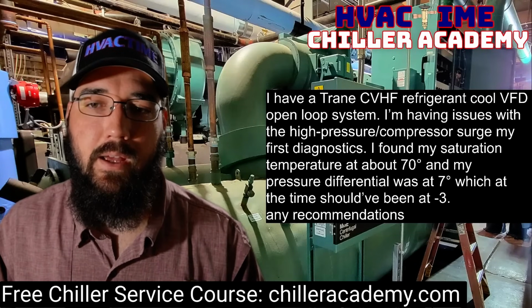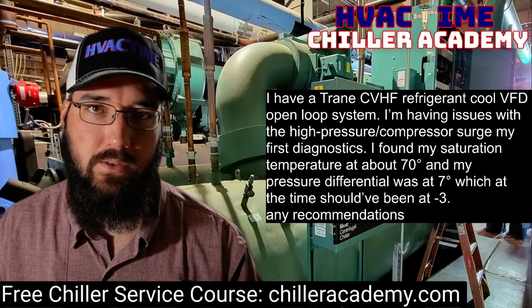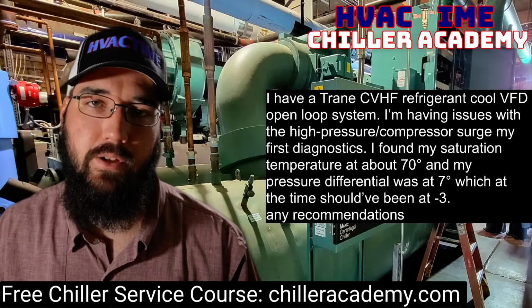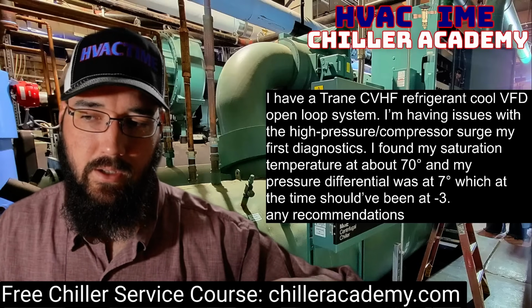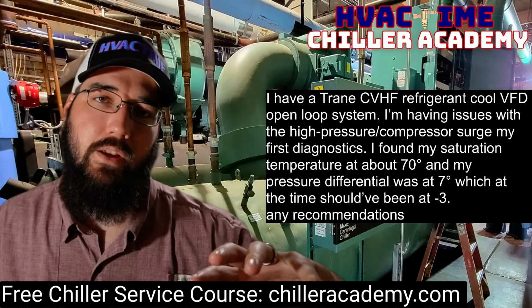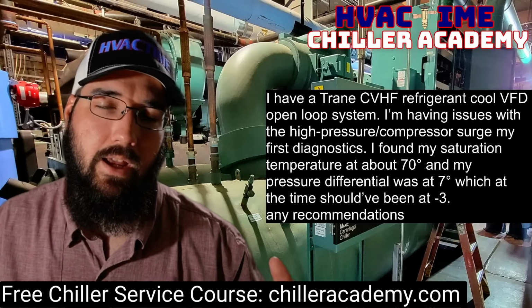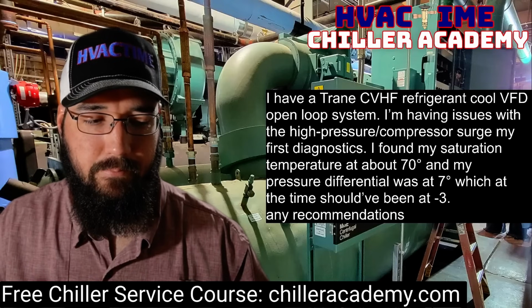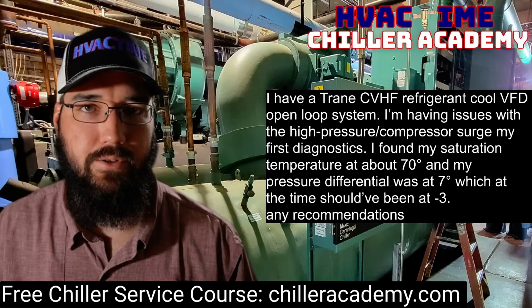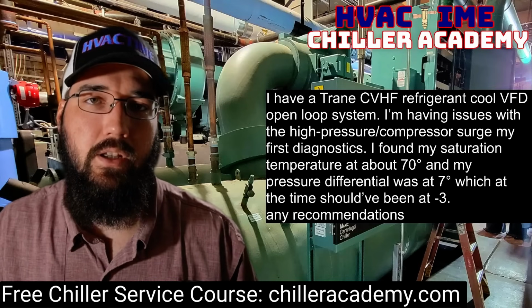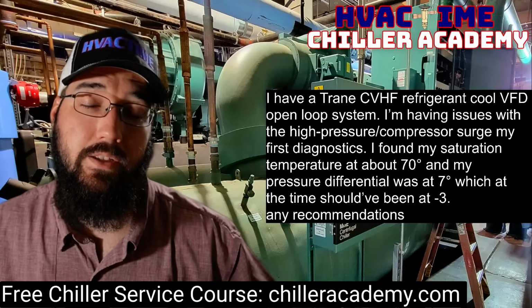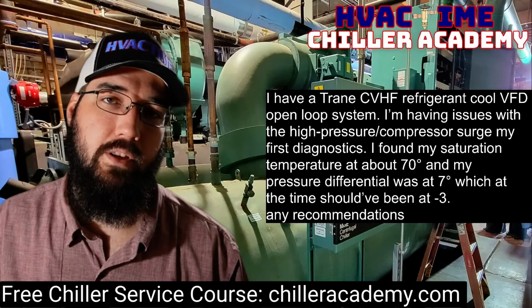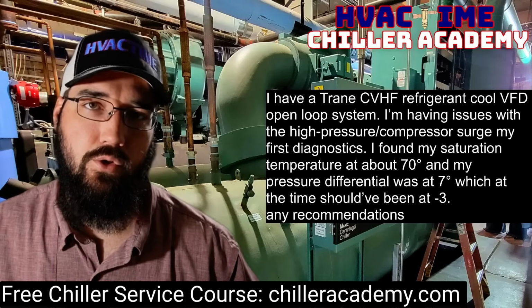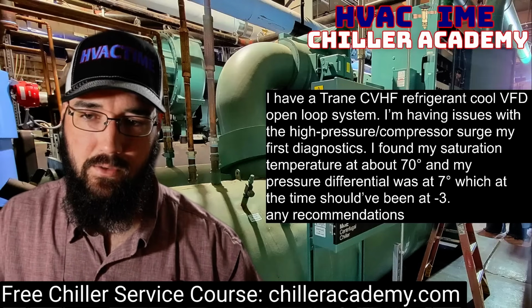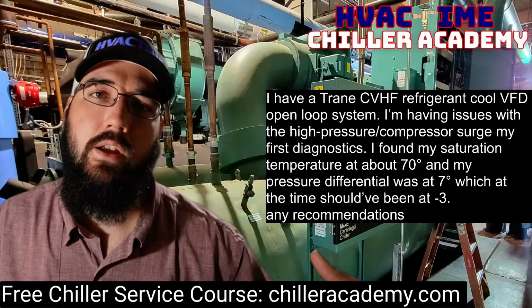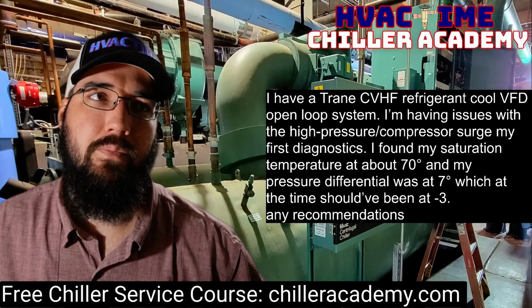Now, ramping that back up makes sense because then we're increasing our GPM and our differential across the heat exchanger. And so having surging and high pressure issues, that makes a lot of sense. Now, I'm assuming you walked into this plant probably already having surging problems from the sounds of the conditions. That is true. So I get the thought process.